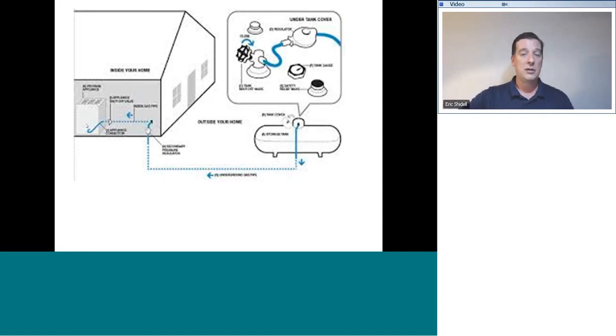That's why commercial gas lines are generally higher pressure. If you have to go 100 yards on a large building from the point where the meter is to the point of use where the appliance is, and you're going to run all of that gas in 7 inches water column, keep in mind that commercial applications are going to have a higher gas demand, you're going to end up with a 4-inch gas line. Or if you run that gas under 2-pound or 5-pound pressure, you can end up with a 1-inch gas line instead to deliver the same amount of fuel under higher pressure.